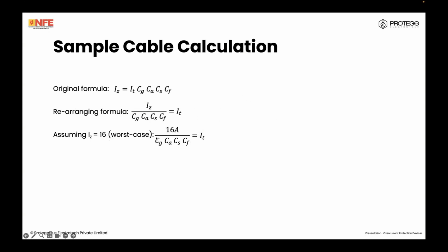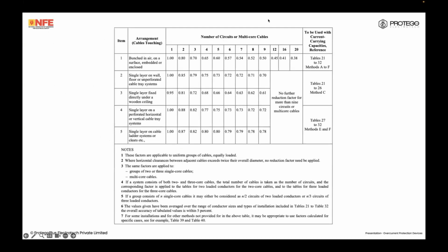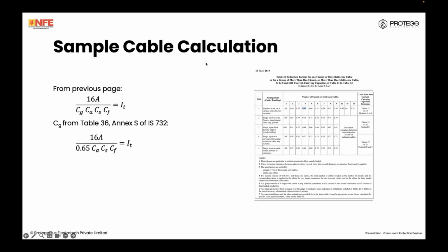So you cannot just choose the value that will actually carry 16 amps. You have to choose a value that is greater than 16 divided by this value. Okay. I said there were 3 other circuits. That is totally 4 circuits. The cable is embedded in a surface. So it's reference item 1, 0.65. I'll just plug that value in right here.